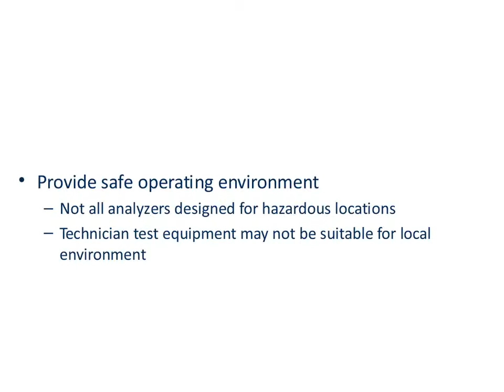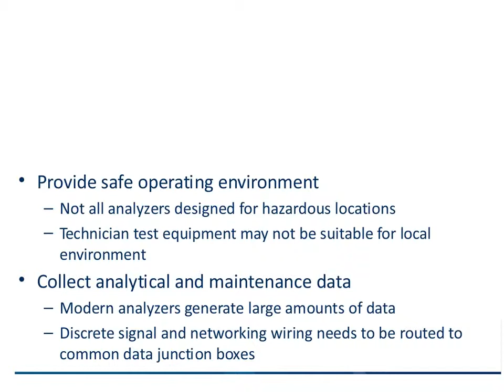And then finally, in this day and age, analyzers generate a tremendous amount of data that's used for process control or environmental monitoring and such. So part of a total package for analyzer system integration is to be able to collect all of this data, collate it, and then transmit it over standard techniques such as field bus, HART, Ethernet, or whatever mechanism is preferred for this particular application.